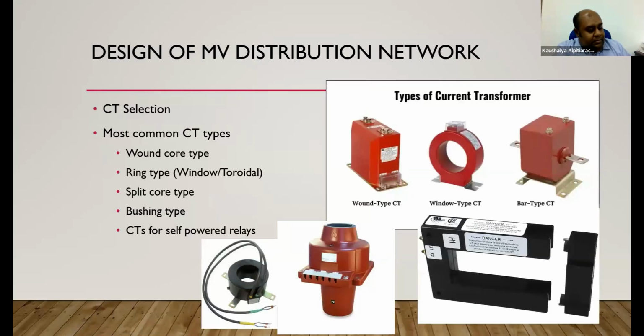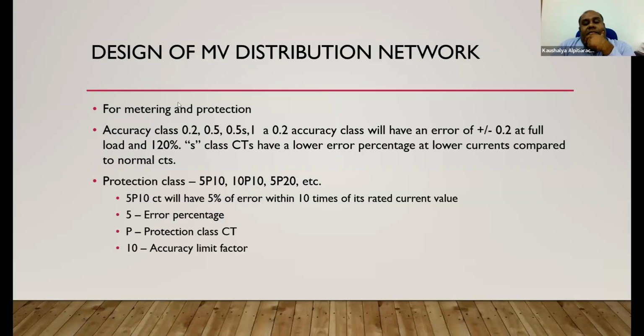CT selection. Common types: wound type CTs, window type CTs, bar type CTs, split core CTs, bushing type CTs, and CTs for self powered relays. This is a bushing type CT, which you use specifically for transformers. For metering and protection, both you need CTs.